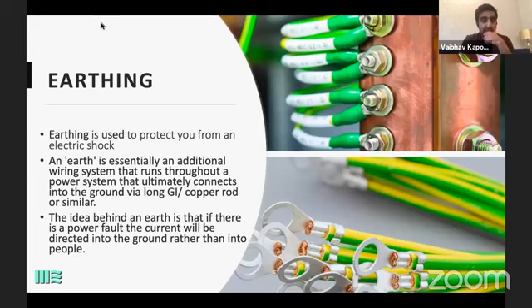So this screen, again, what I wanted to show is that on the top picture, this is a very common earth that we are doing. If you see, there are galvanized iron rods that we have made. These are usually 4 feet to 6 feet. There is a connection between the earthing wire and the rod, which is done by a proper lug.